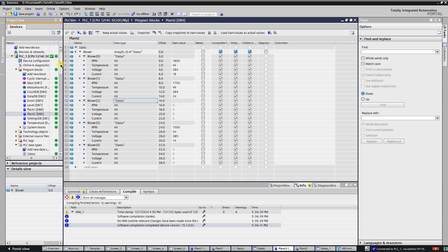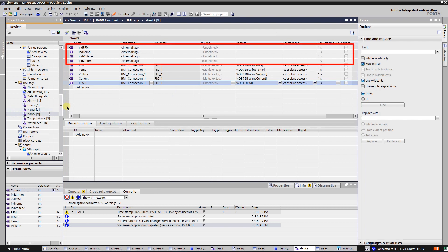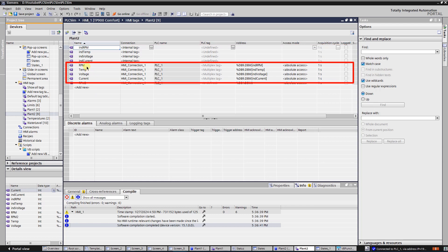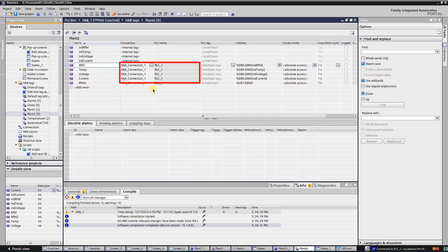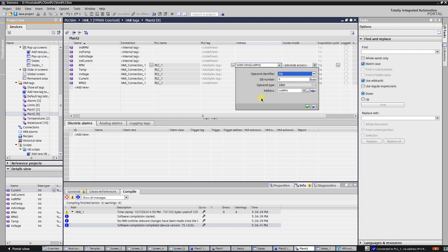Switch to the panel and create one more tag table. Create internal index tags for each reading and a multiplex tag for each reading. Select your connection and make sure that the access mode is absolute access. Expand the cell in the address column and set the right DB number. By the way, you can create an index for the DB number as well. Set the HMI tag for address and select the created index tag.